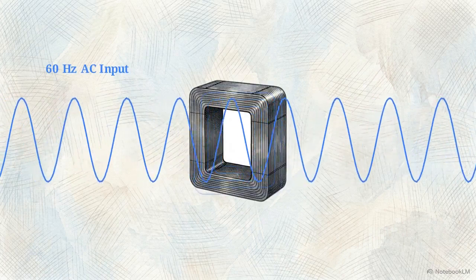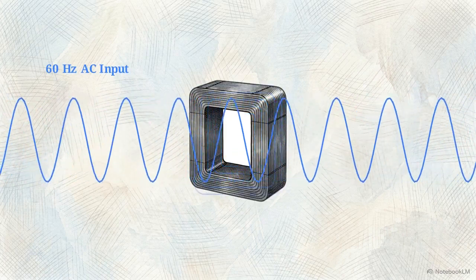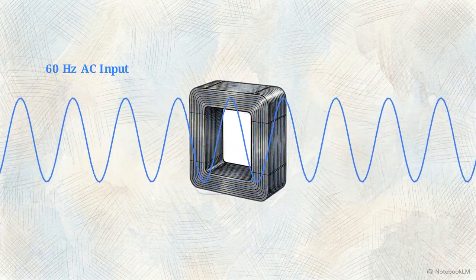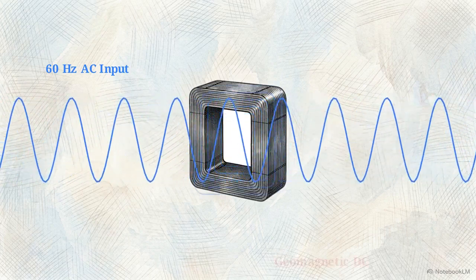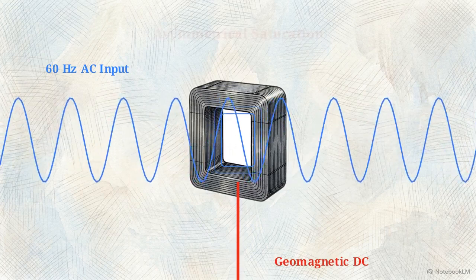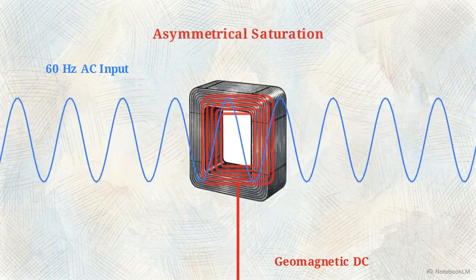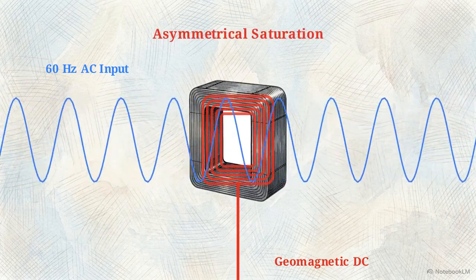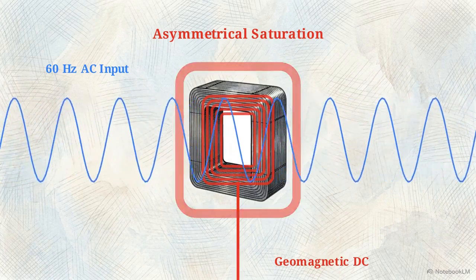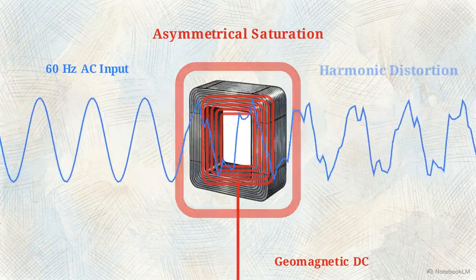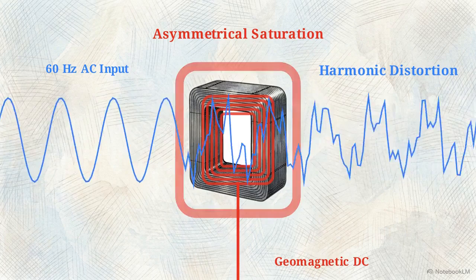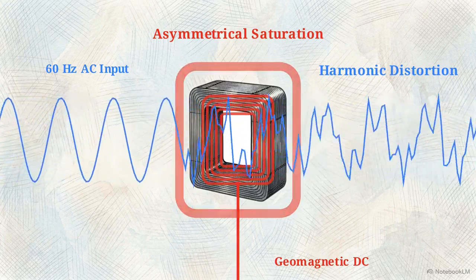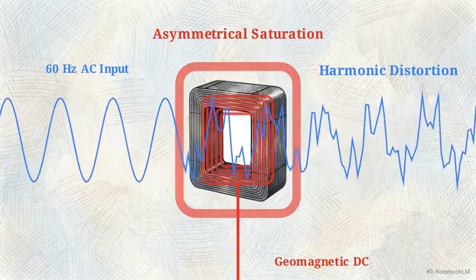Normally, the alternating current creates and releases magnetic flux in a continuous, balanced cycle. The core magnetizes and demagnetizes 60 times every second. The invading DC current causes asymmetrical saturation, constantly adding magnetic flux without allowing it to release. Pushed to its absolute magnetic limit, the core can no longer absorb energy. Incoming alternating current hits this barrier and distorts, unable to pass as a clean wave.